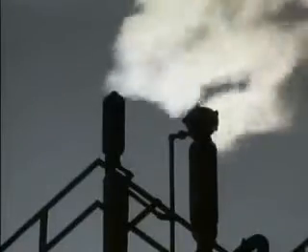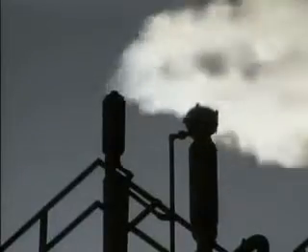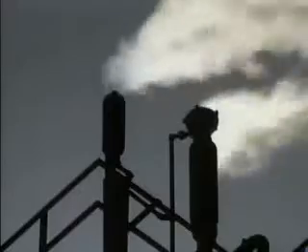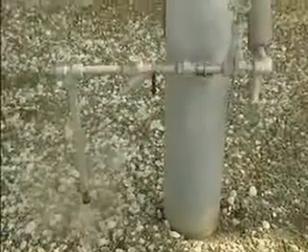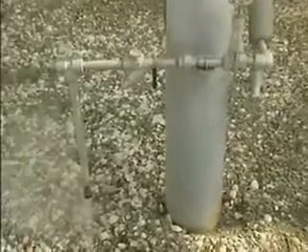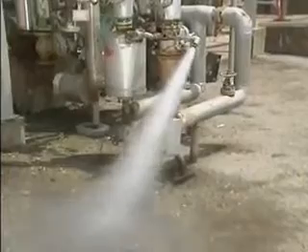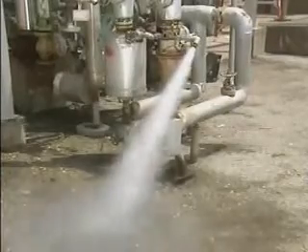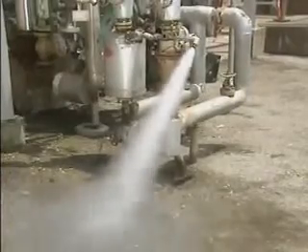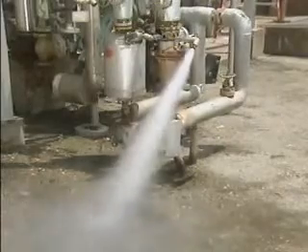Live steam is produced in the steam system's boiler. It's usually discharged with more force than flash steam is, and it has no center core of hot condensate. If it's working properly, a steam trap should be discharging hot condensate with some flash steam. But if it's discharging live steam, the trap isn't working properly, and it must be repaired or replaced.